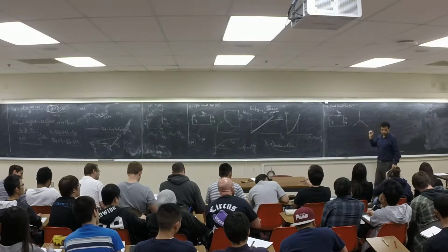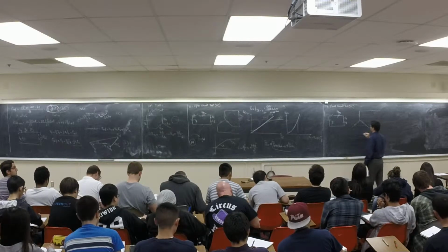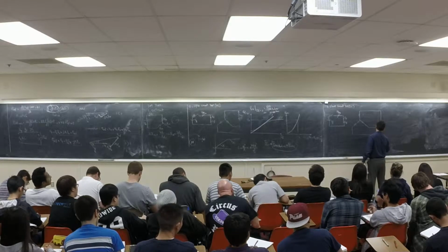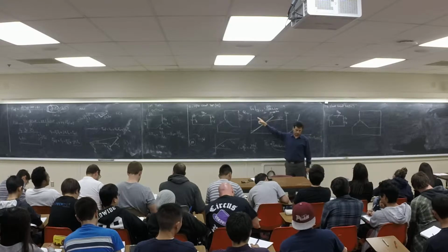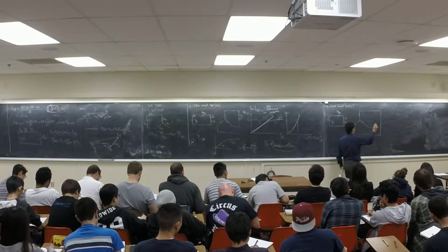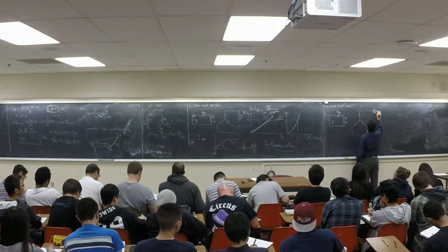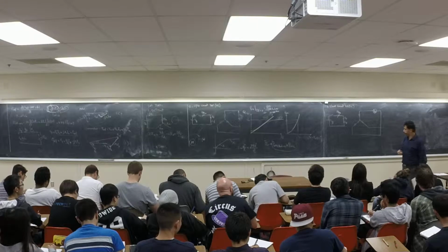This is the stator of the machine, right? We're going to do what? Short. What did I measure here? I measured the open circuit voltage, right? Here I'm going to measure the short circuit. Right, this is the ammeter here. It's going to measure the short circuit current.